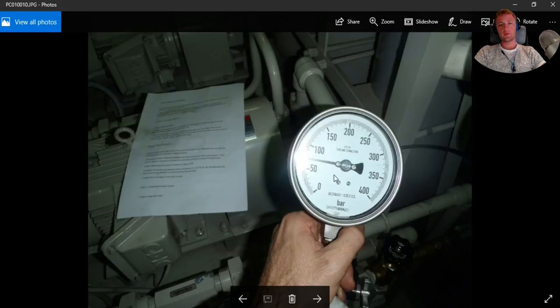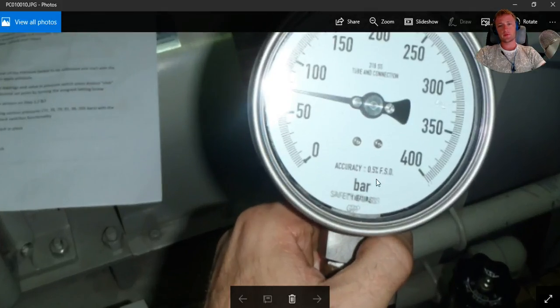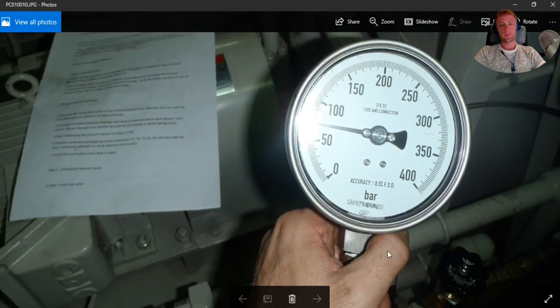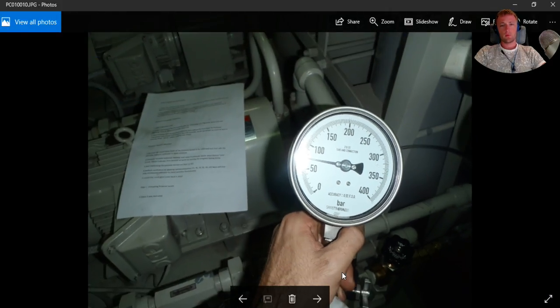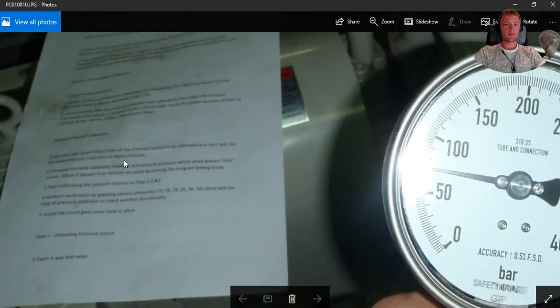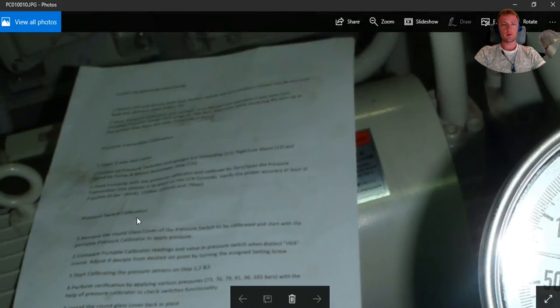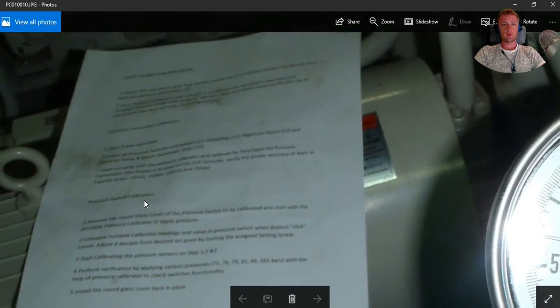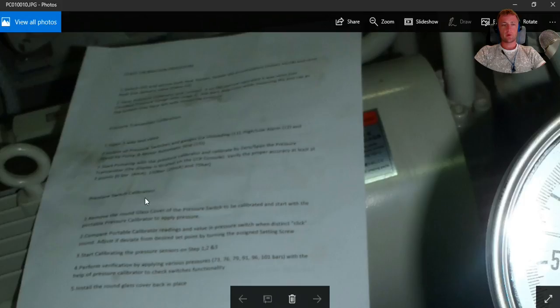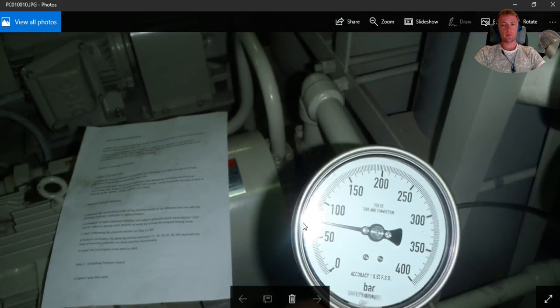Here with this equipment, with this calibrator and this gauge which is calibrated with accuracy of 0.5 percent, we will calibrate. Here are the instructions how to calibrate, and in the manual you can find the pressures, the calibration procedure, everything.